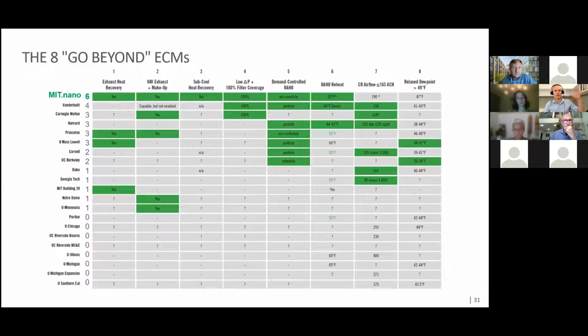As an example, a typical lab building of course uses variable volume. Why would you have a lab running constant volume all the time? If you're shutting the sashes on fume hoods, you want the airflow to turn down, or when people aren't in the space, you want it to turn down. But clean rooms have such hazardous chemicals and such critical environmental controls that historically, in a lot of cases, clean rooms were not variable volume - they were just constant volume.